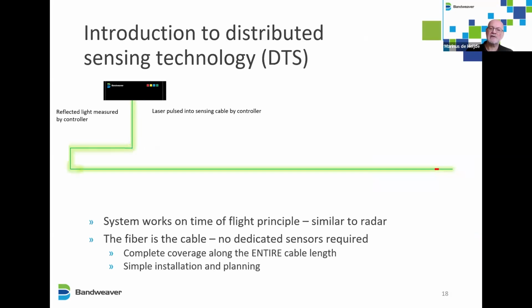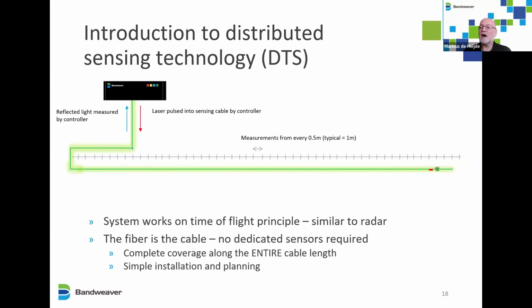So a little schematic with an example of how this works. What we're doing is sending a laser through a cable. This travels at the speed of light, which is roughly 300,000 kilometers per second, and we measure the reflection of this light. If the temperature changes by 0.1 degree, we can see the location, roughly half a meter to a meter accurate. So it's a very accurate system over long distances, and therefore very suitable for conveyor belts.